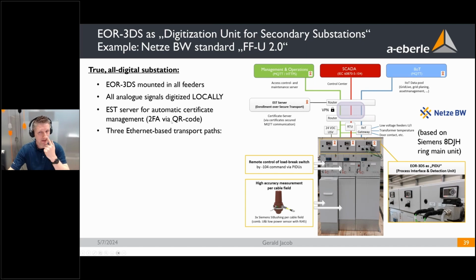So you can see here in the overview the compact switchgear station in the middle. You see some arrows in each cable field. 3 bushings are installed for all 3 phases, and they are directly connected via Ethernet cable to the earth fault indicators, EOR-3DS. We have here a remote control, so a motor control unit installed in the cable fields, and via the 104 protocol, the devices get a command to open or close the load breaking switch. They pull the relays in direction of the motor control unit, and in the end the load breaking switch is switched off and on.